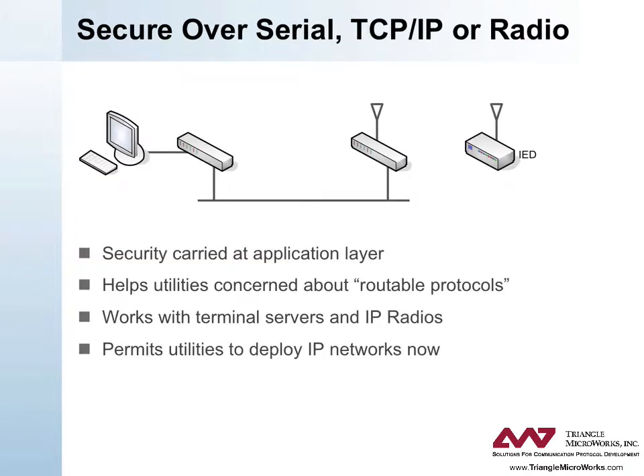Because the DNP3 authentication messages travel at the application layer, they are carried with the rest of the DNP3 message when terminal servers or IP-based radios are used. Some utilities are using these devices to avoid using routable protocols in some portions of their SCADA networks. Using DNP3 Secure Authentication ensures that there is a security solution even when terminal servers or IP radios are used. One advantage of DNP3 Secure Authentication is that it allows utilities to deploy DNP3 in a secure fashion over IP networks, providing an evolution path to other IP-based automation solutions such as IEC 61850 in the future.